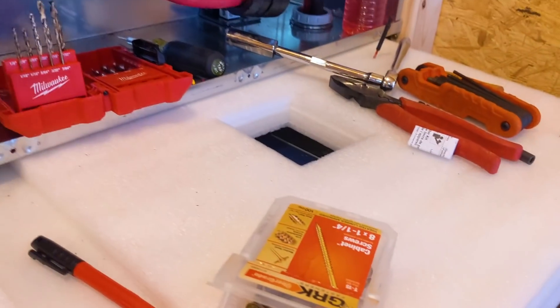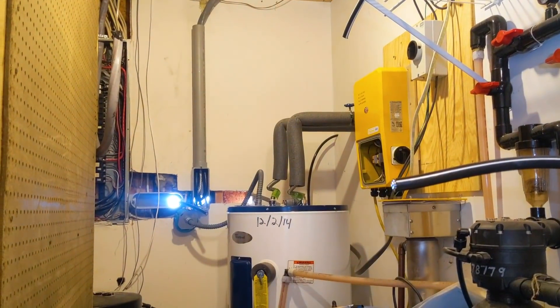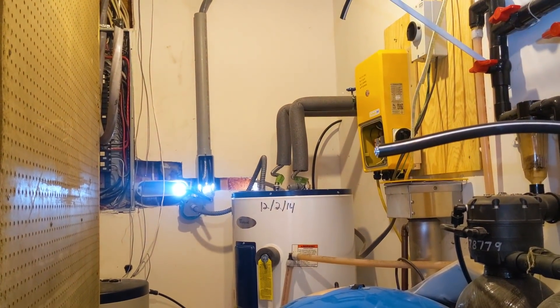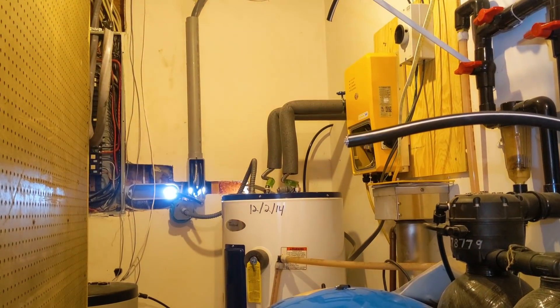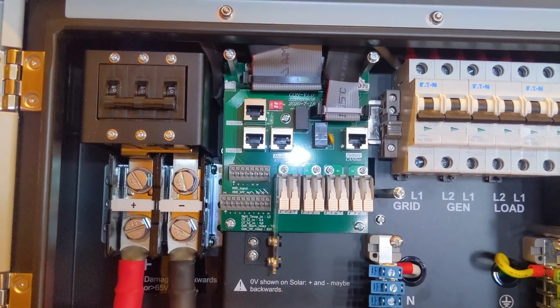This is kind of the fun part of solar — just hooking it all together. We've got a battle over here in the corner getting the SER wire out to a disco fuse disconnect. We need to get the CTs — we always seem to forget the CTs. Especially on somebody connected to utility and dealing with TVA, there's no exporting with batteries. The CTs allow you to do everything behind the meter. You hook the CTs into the terminal block, set it to limited power to home, and this will be the master with the slave, controlling and selling to the house as much power as is being used at any one time.